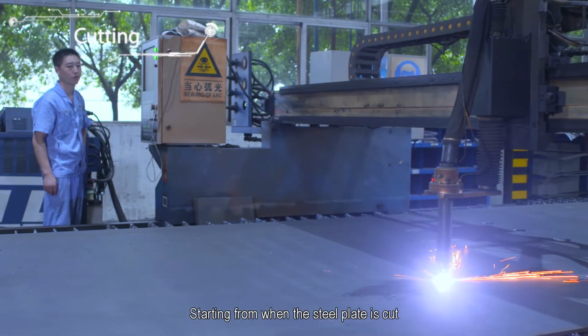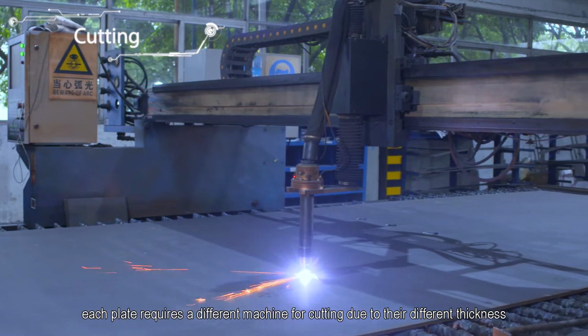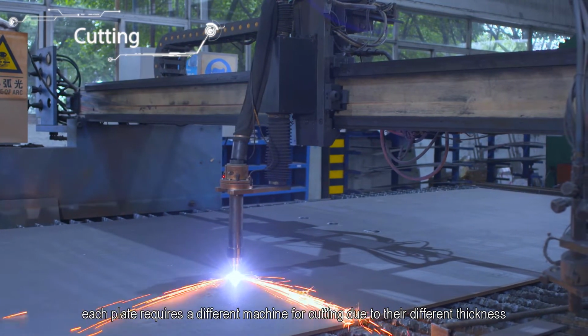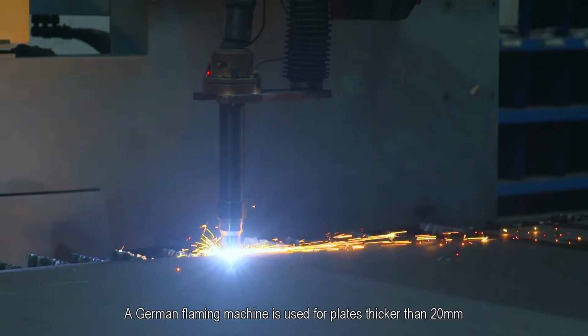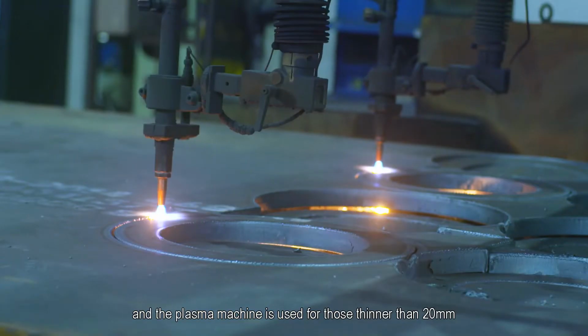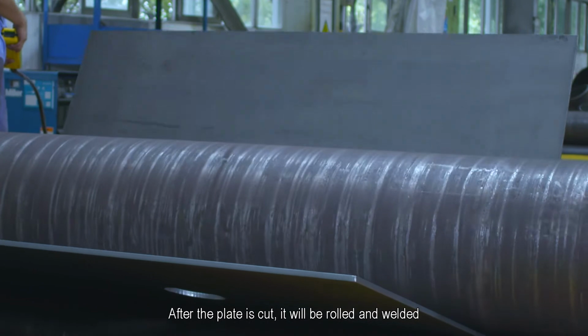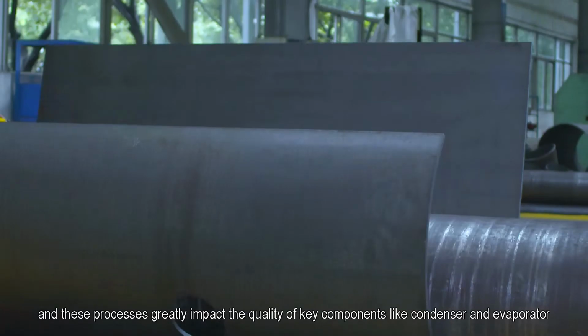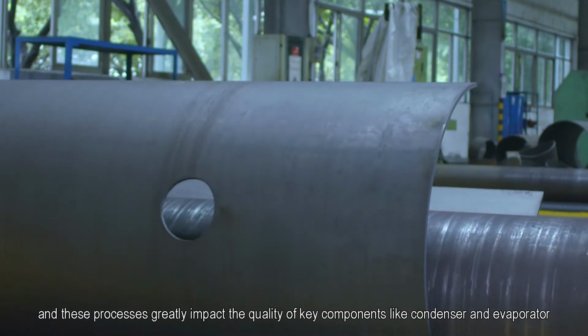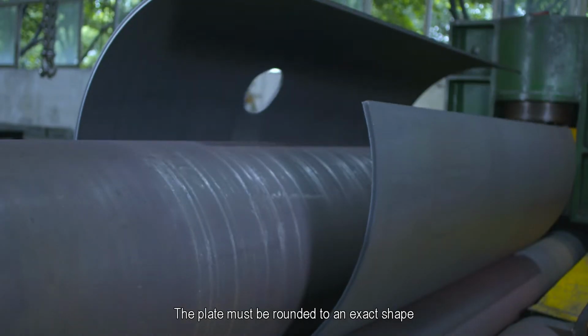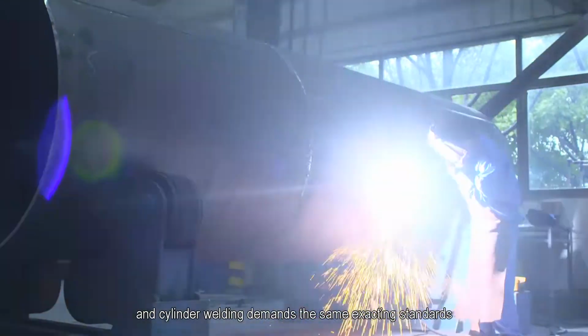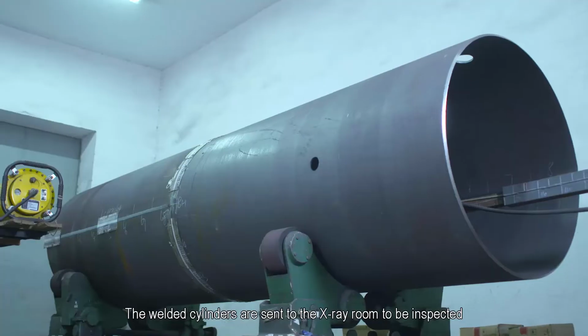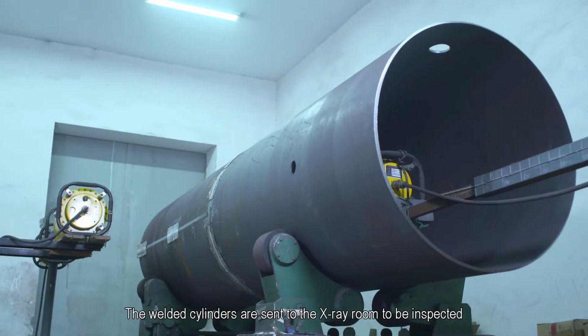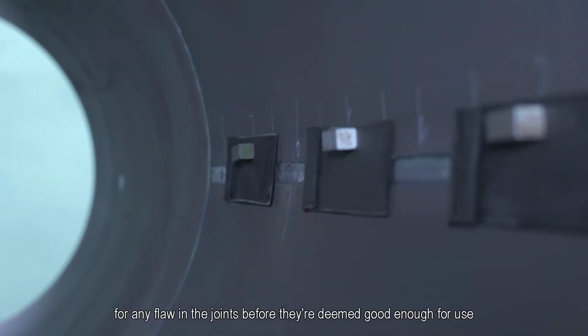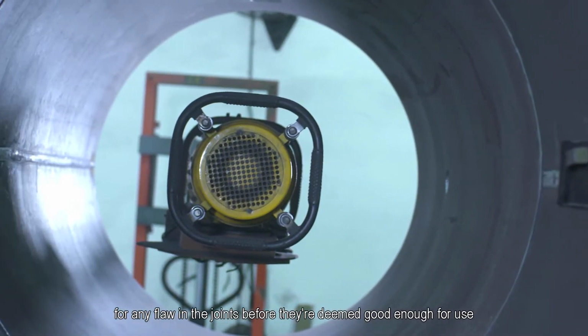Starting from when the steel plate is cut, each plate requires a different machine for cutting due to their different thickness. A German flaming machine is used for plates thicker than 20 millimeters, and the plasma machine is used for those thinner than 20 millimeters. After the plate is cut, it will be rolled and welded, and these processes greatly impact the quality of key components like condenser and evaporator. The plate must be rounded to an exact shape, and cylinder welding demands the same exacting standards. The welded cylinders are sent to the X-ray room to be inspected for any flaw in the joints before they're deemed good enough to use.